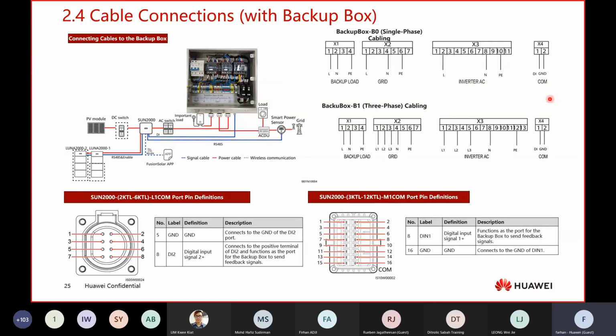And this one is COM. This COM is actually how our backup box operates, how the SUN2000 will operate during an AC loss. This sends a signal to the inverter to show that there is no AC present on that side, maybe an AC blackout. Then the inverter will start to operate in off-grid mode.